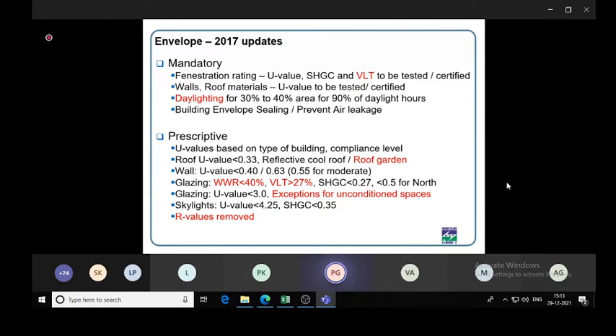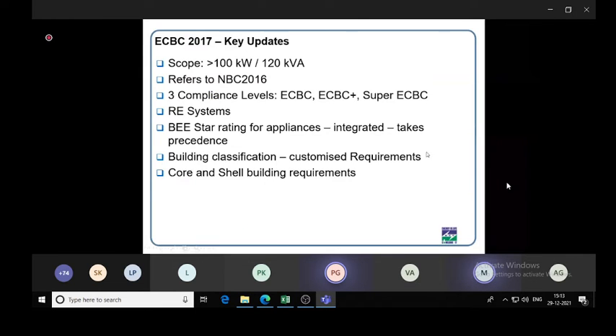So to summarize the ECBC code for commercial buildings, any building more than 100 kilowatt or 120 kVA, or more than 2000 square meter in case of Tamil Nadu, needs to comply with ECBC. And we have 3 levels of compliance. ECBC is mandatory and the other 2 are voluntary.